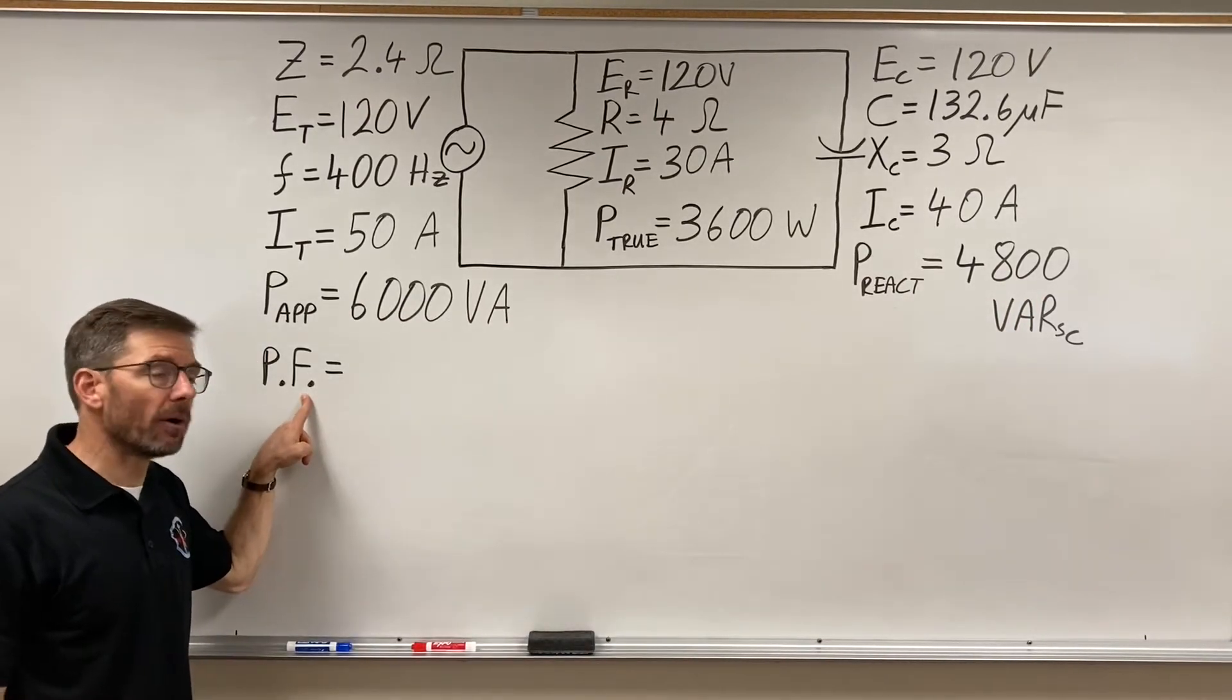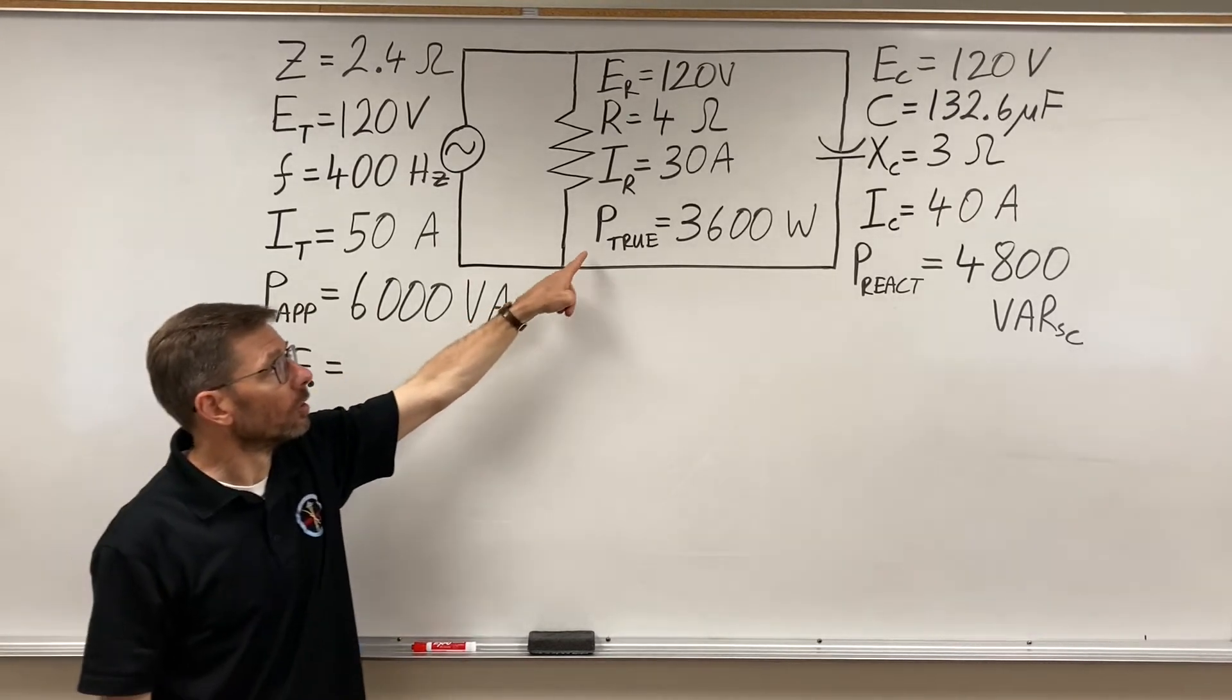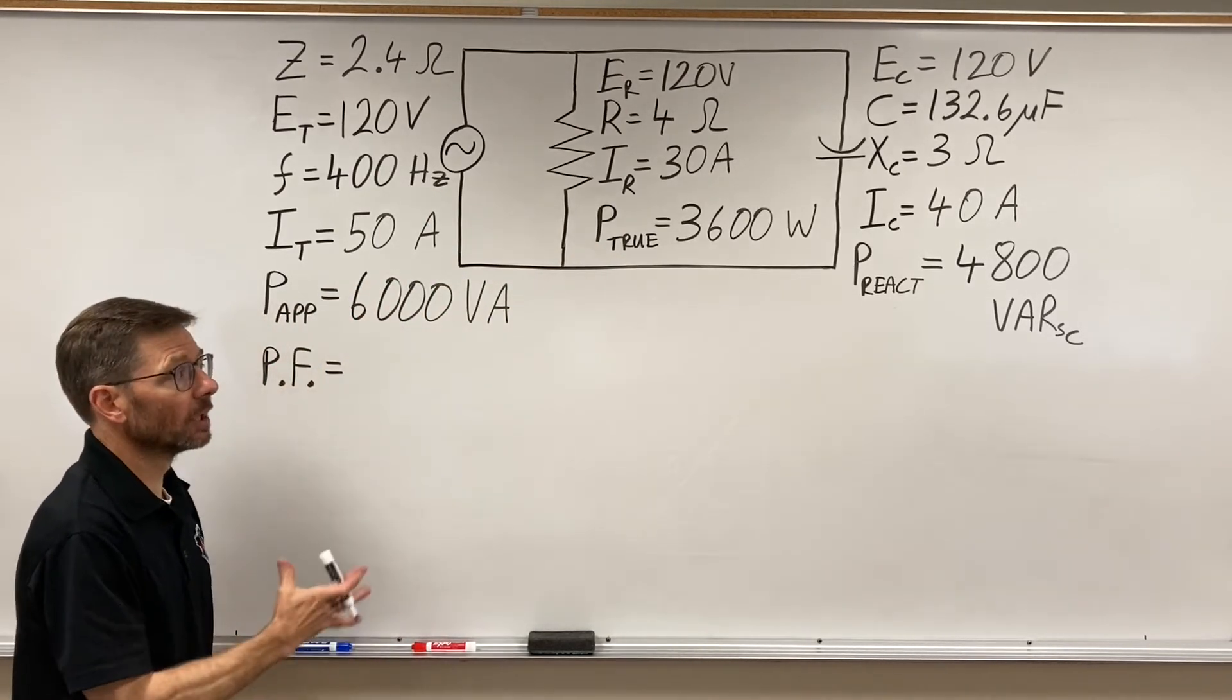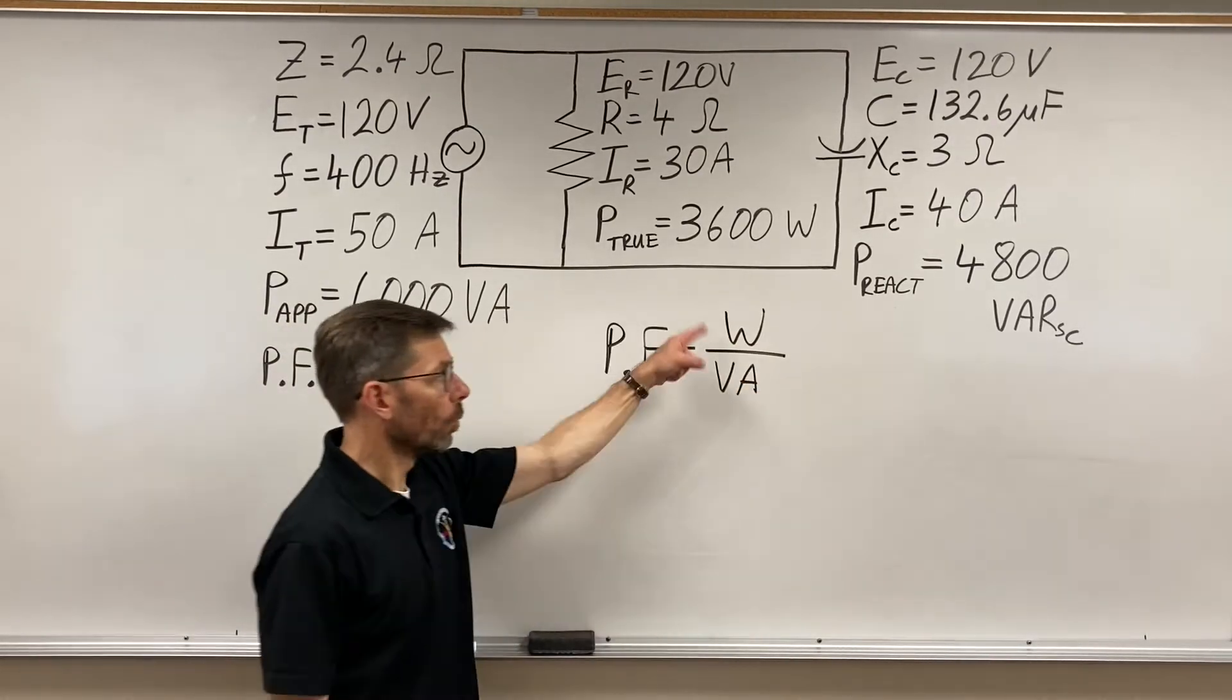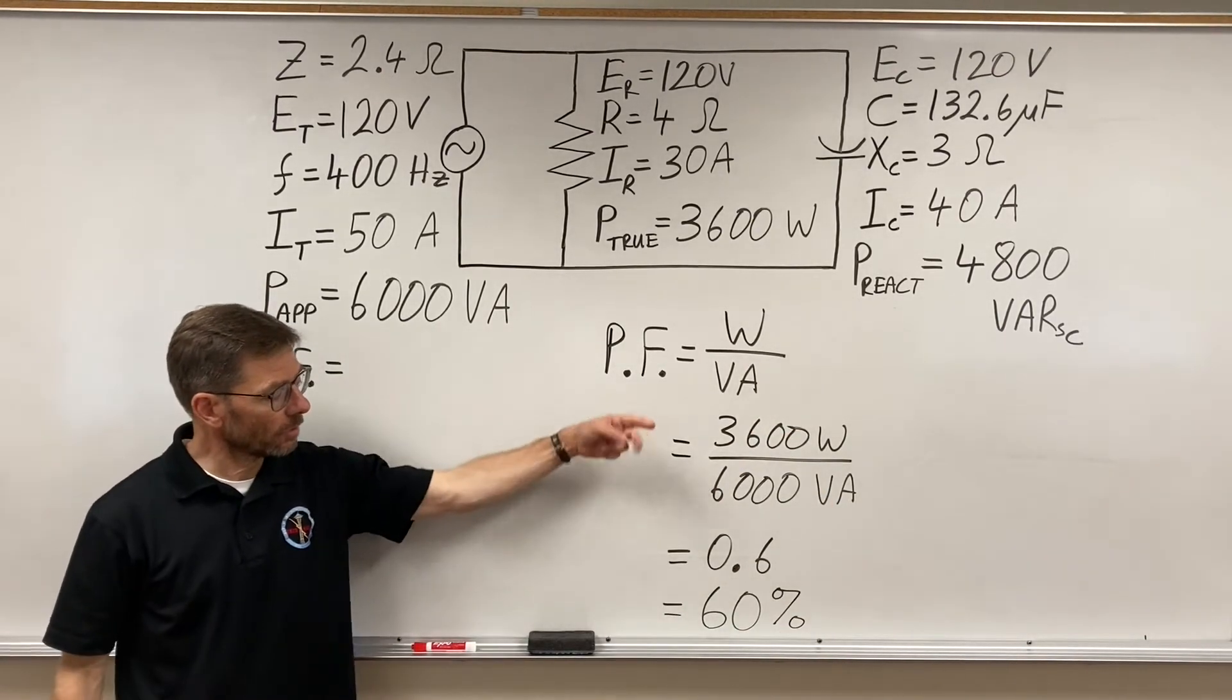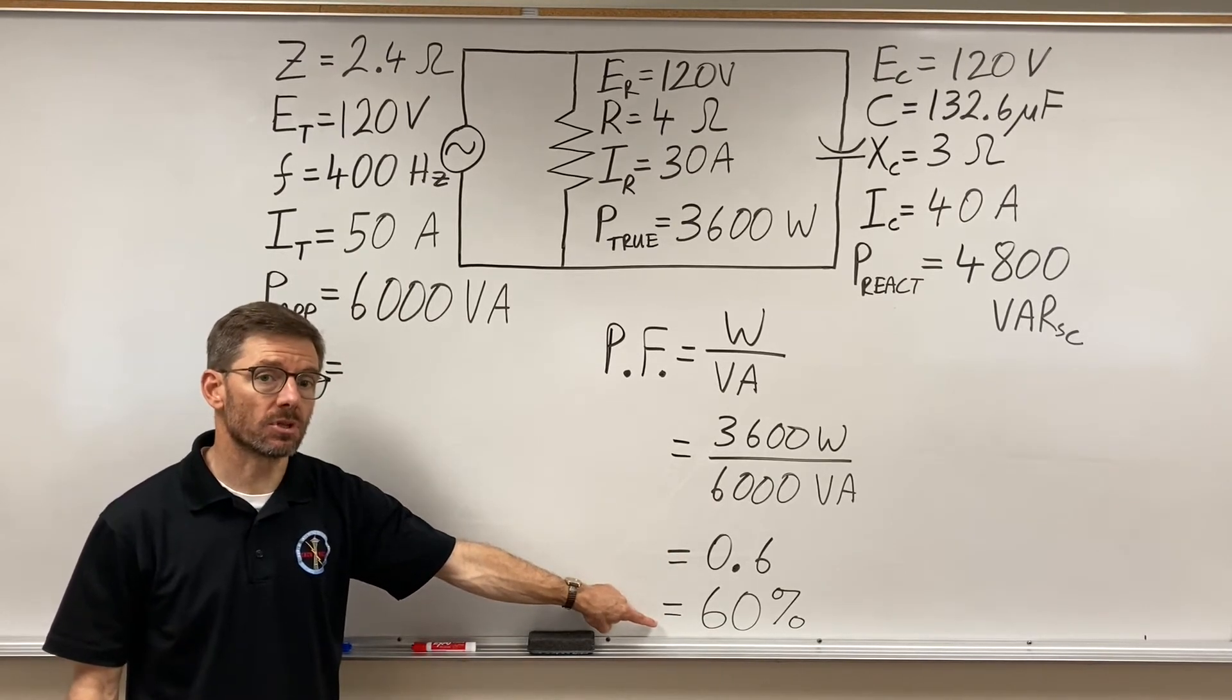And what's my power factor? Again, my ratio of real work being done compared to the power that I need to put into the circuit. A really important equation: watts over VA. Calculate that out, we get 0.6, which equates to 60%.